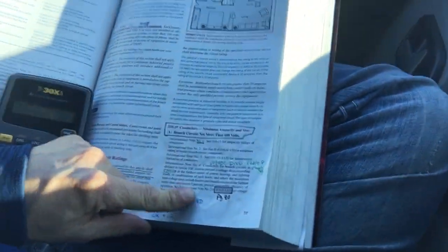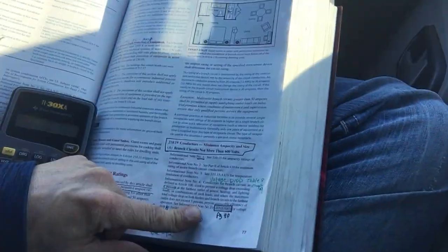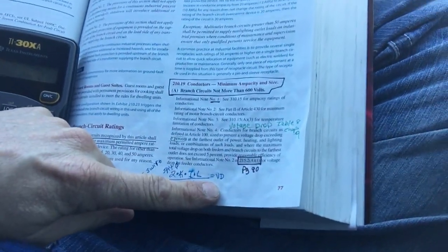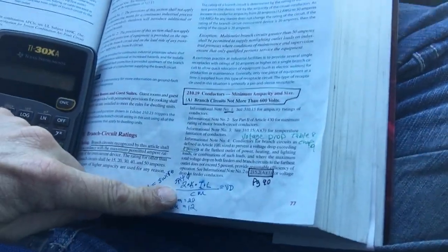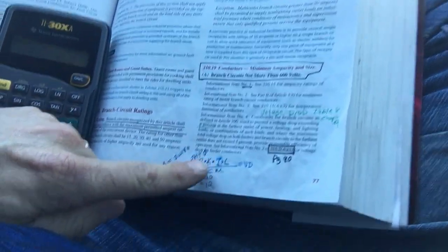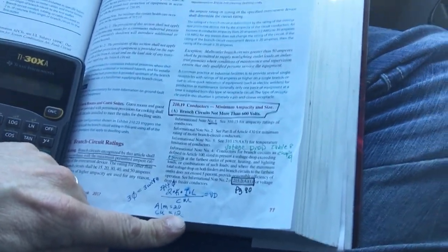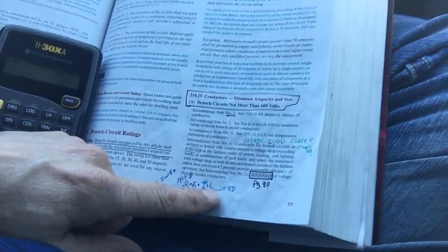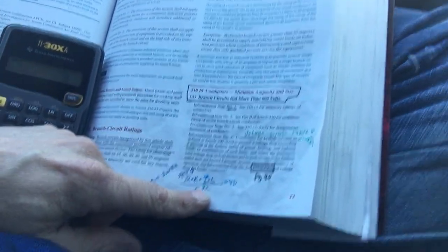For your branch circuit it's 3%, and 5% for your feeders and branch circuits combined. Here's your voltage drop formula: K times circuit length divided by circular mill equals voltage drop. In this case you're using three conductors for three-phase, so you do three times the constant K — which for copper is 12 — times amps, times length, divided by circular mill from Chapter 9, Table 8.